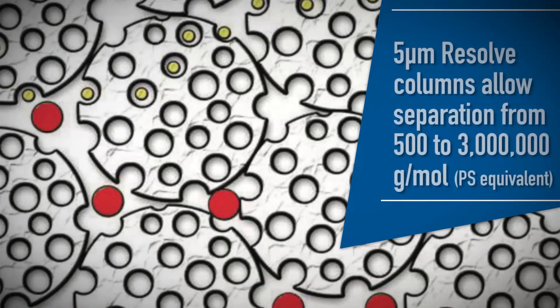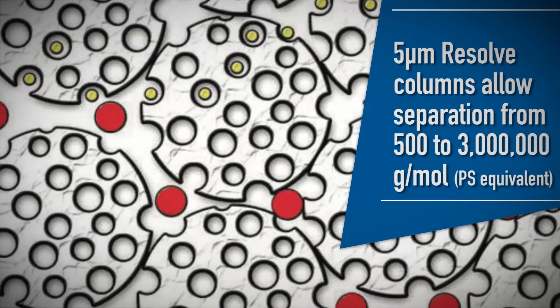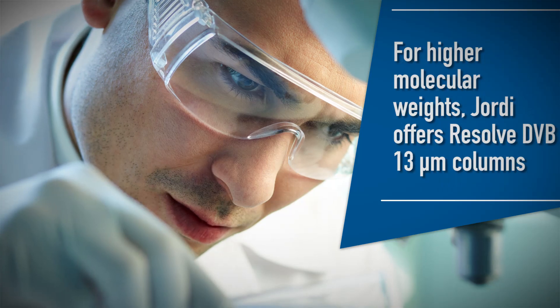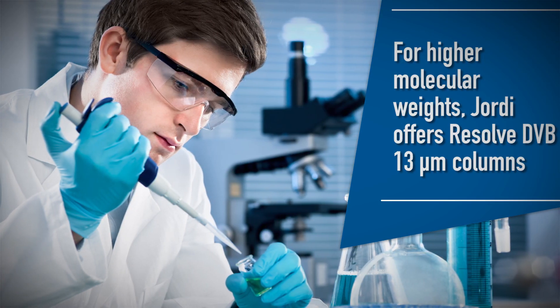5-micrometer Resolve Columns allow separation from 500 to 3 million grams per mole. For higher molecular weights, up to 12 million, Jordi offers Resolve DVB 13-micrometer columns.